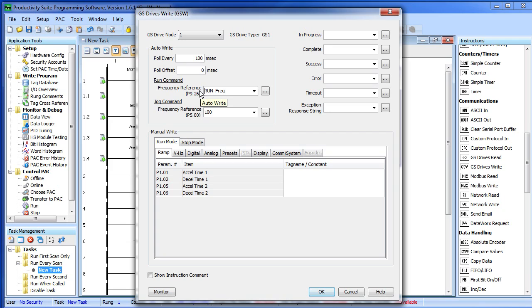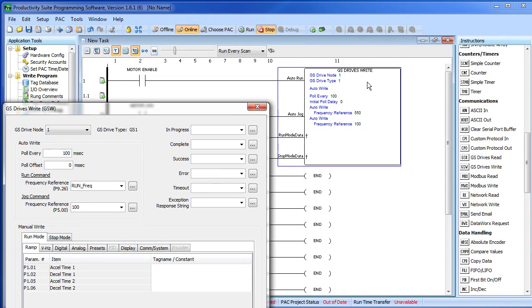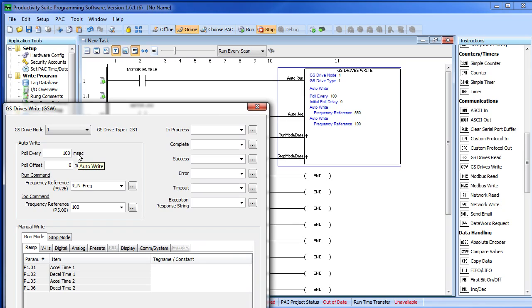So now in my ladder code, if I change the value of run frequency and the instruction is enabled via the auto run, then the drive will react accordingly on the very next polling cycle. It will ramp up or down to the new frequency per the ramp rates I defined in my configuration.